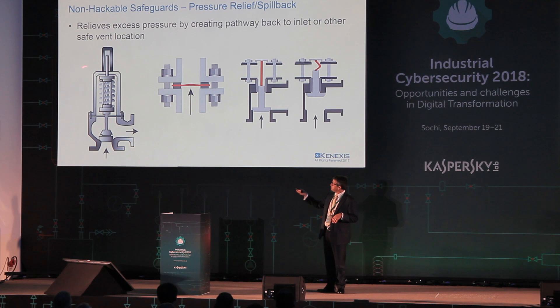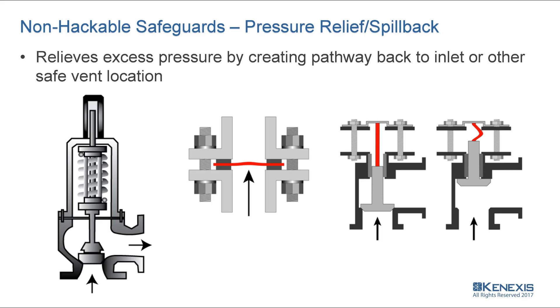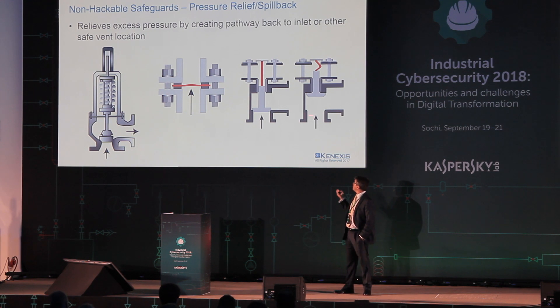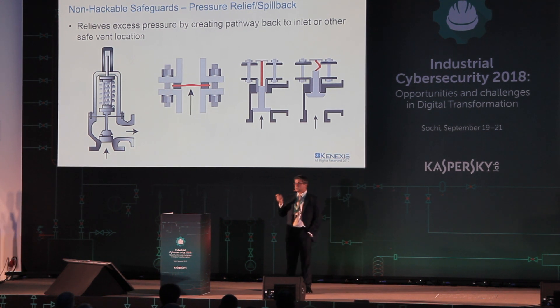What if I don't want to do that? There are other non-hackable safeguards. For pressure relief, you can use a spring-based pressure relief valve: as the pressure of the material gets higher, it pushes on the plug, overcomes the spring force, and allows material to escape to a storage tank. Other similar options include a rupture disc — a sacrificial membrane that pops open when pressure goes high — and a buckling pin device that works similarly to the relief valve, except instead of a spring, a pin bends and breaks when the pressure gets too high. None of these things can be hacked.